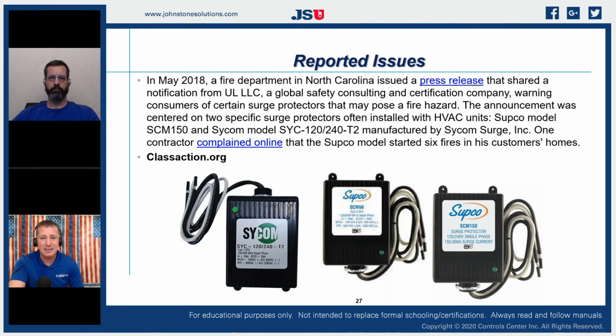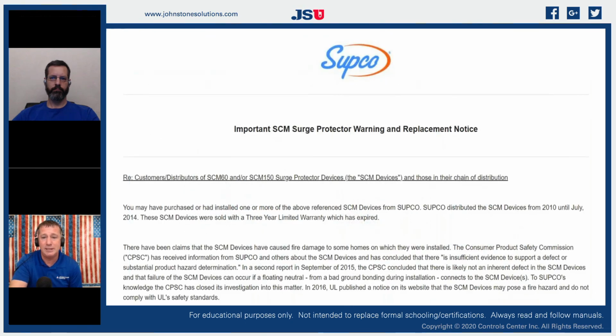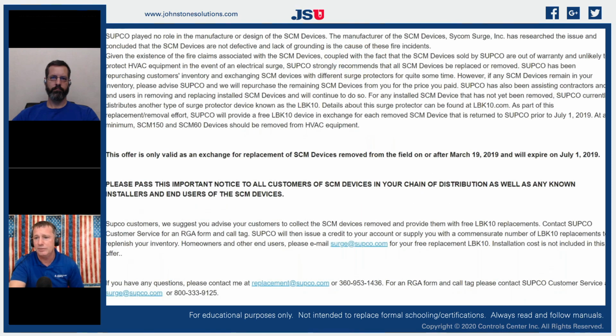And we had some incidents with the cases on these leaking. So it wasn't that the component itself had failure issues. It was that the company that built the shell for it didn't seal very well, and they were able to get moisture inside of those. So Supco had actually released a warning that they were having failures with those, and that up until July 1st of 2019, they were replacing those and upgrading those free to that LBK10 that I showed you a while back. So the LBK10 is the replacement for all these.